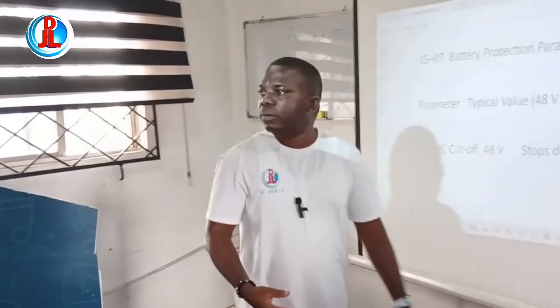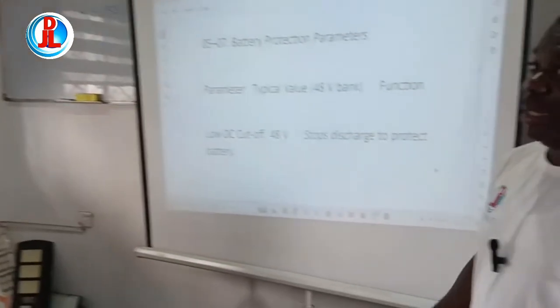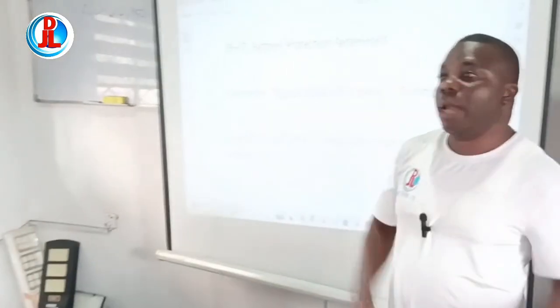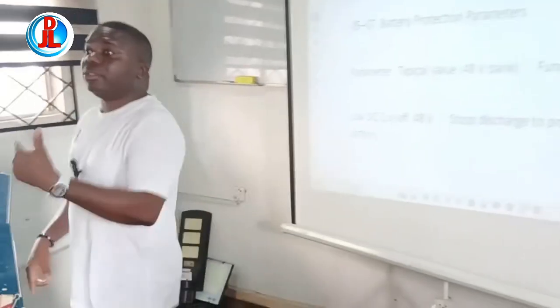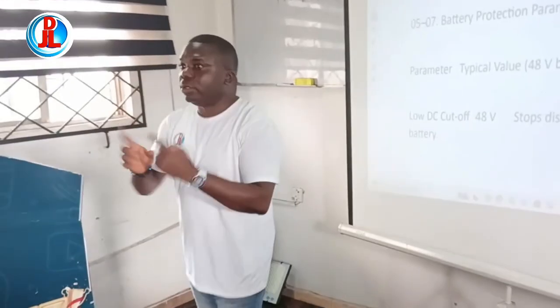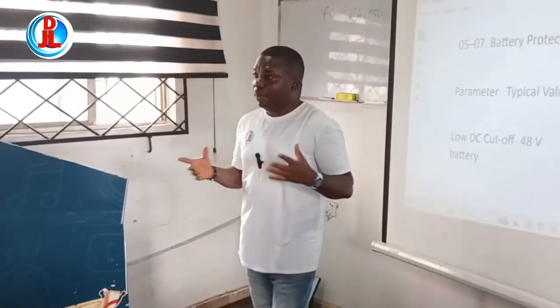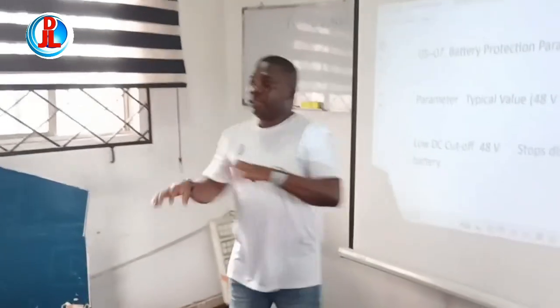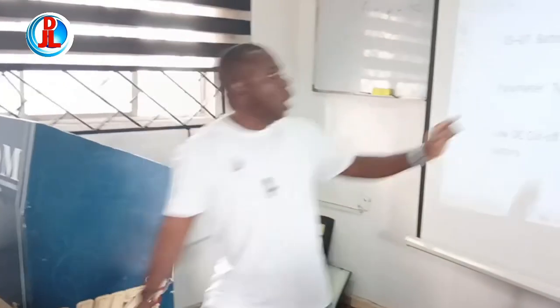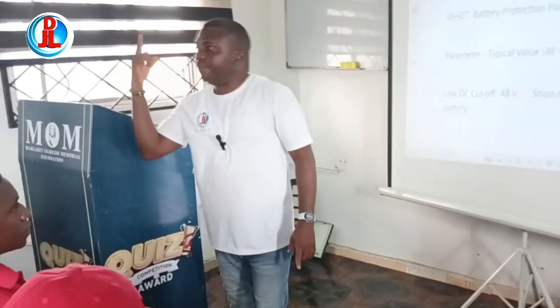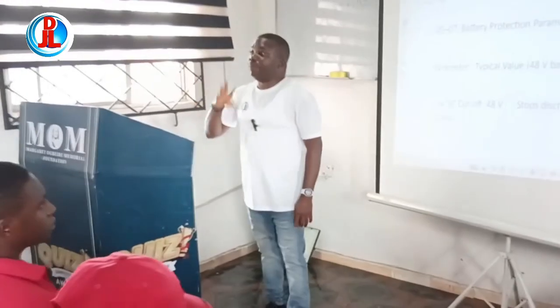Now, low cutoff for lithium battery. Be attentive. Low cutoff for a 48 volts lithium battery is 48 volts. Because your lithium battery could be like 52.5, around 51.5 or so. When you get to 48, that is the cutoff, not like low cutoff for tubular battery, which is 10.5 each. Some use 11, depending on what you set, which is 44.